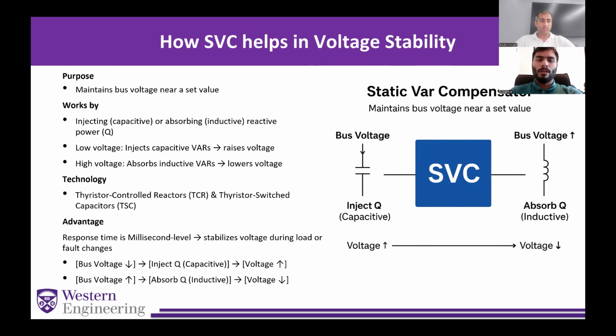In this slide, we will discuss how SVC helps in voltage stability. SVC purpose is to keep bus voltage near a set value by dynamically controlling reactive power. When voltage drops, it injects capacitive reactive power to raise the voltage. When voltage rises, it absorbs inductive reactive power to lower it. Using thyristor controlled reactors (TCRs) and thyristor switched capacitors (TSCs), the SVC adjusts the thyristor's firing angle to precisely control the amount of reactive power injected or absorbed. This millisecond level response allows it to stabilize voltage instantly during sudden load changes or faults, preventing dips, surges and instability in the system.